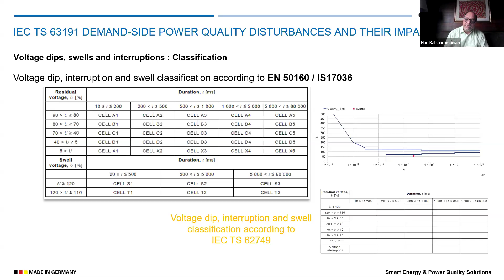There is another new standard called IEC TS 62749, which is making it simpler. It puts both sags and swells in one table, which is on the left side of your screen down below. I have made it a very small table because it is an emerging way, but we can give the number of times my voltage has crossed 80 to 70%, 10 times in a month or in a week. We have to start giving this information: when it happened, how long it happened. So 70% it went low, 40% it went low for 10 milliseconds, 20 milliseconds. So the depth and the time need to be clearly defined and we can create it as a report. And that's what EN 50160 or IS 17036 does.